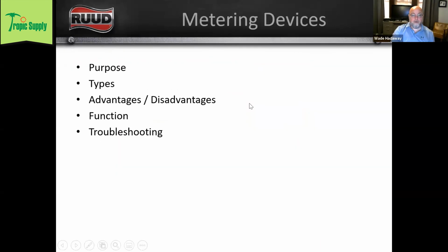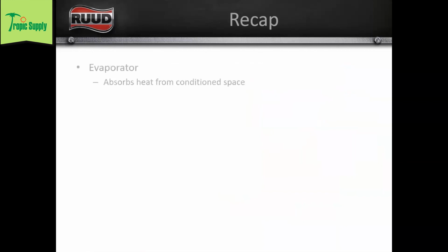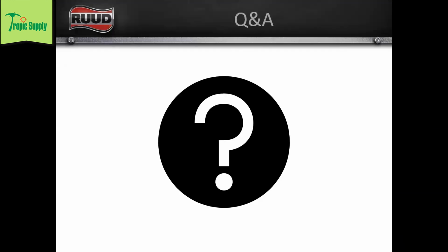Any other questions? I'm going to go ahead and just zoom up to the end. Yeah, I got one more question. Say for instance, you've changed the compressor. What would be your recommended way of recharging the system? So first, you'd weigh the factory charge back in.